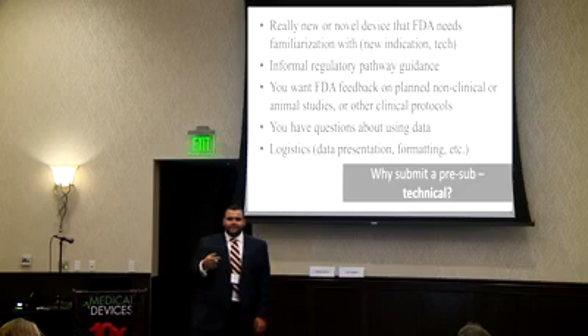So there are a lot of catheter standards, recognized consensus standards for catheters, right? There's a lot of catheter guidance. So imagine you sit down as an R&D engineer with a brand new catheter and you have like 700 documents that tell you what your catheter needs to do. You can start figuring out what your development path is for that specific catheter, picking and choosing all these standards, putting together a test plan and saying, hey, FDA, what do you think about this test plan? You get comments on that, versus freaking out for 6 months, going to submission and being told, oh, you forgot this specific standard for tensile tests or leak testing. Well, crap, we could have avoided that.